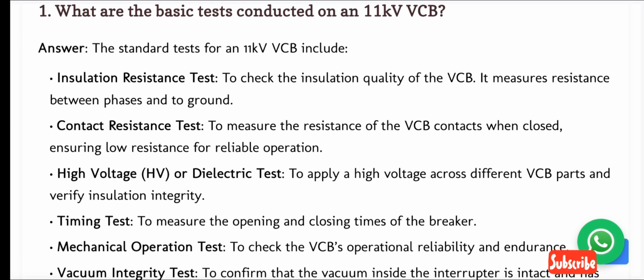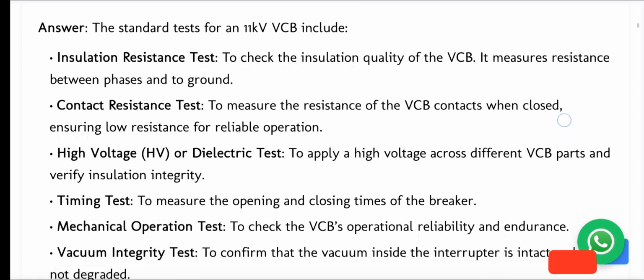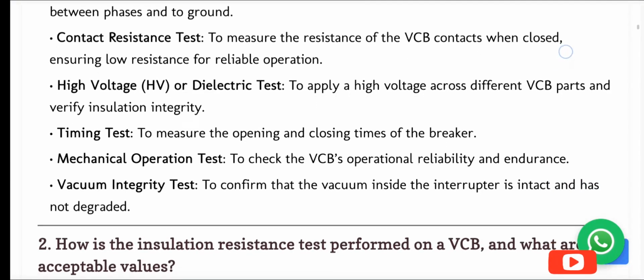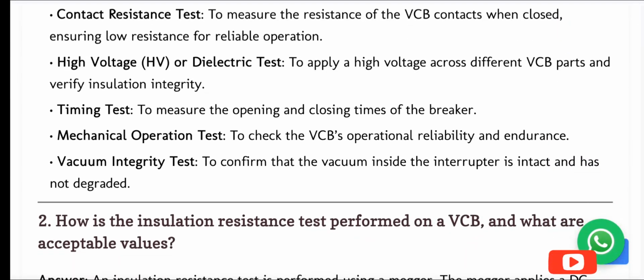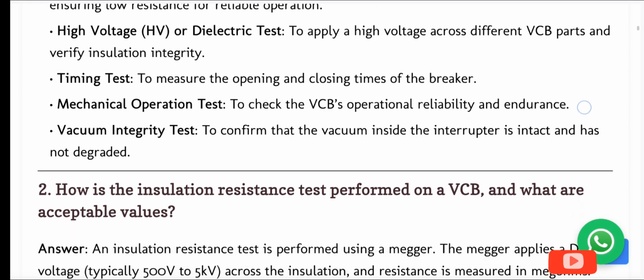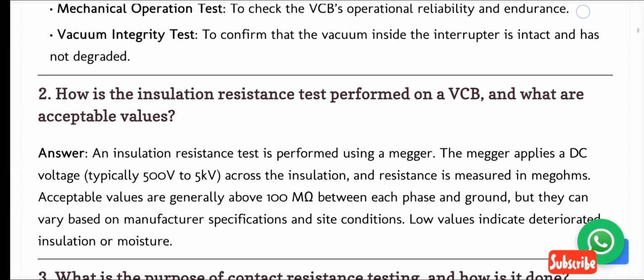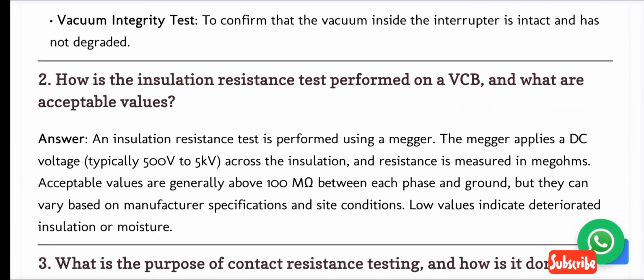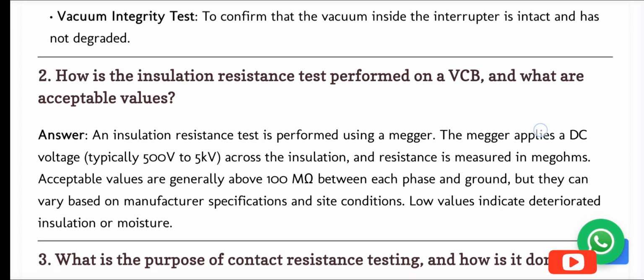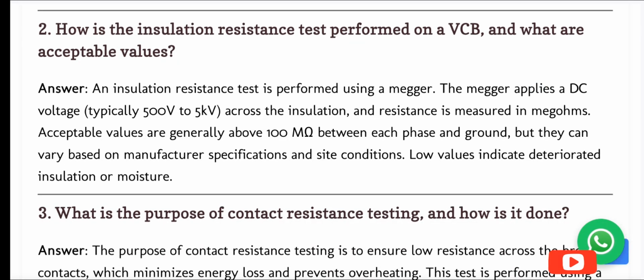Timing test, to measure the opening and closing times of the breaker. Mechanical operation test, to check the VCB's operational reliability and endurance. Vacuum integrity test, to confirm that the vacuum inside the interrupter is intact and has not degraded. 2. How is the insulation resistance test performed on a VCB, and what are acceptable values?